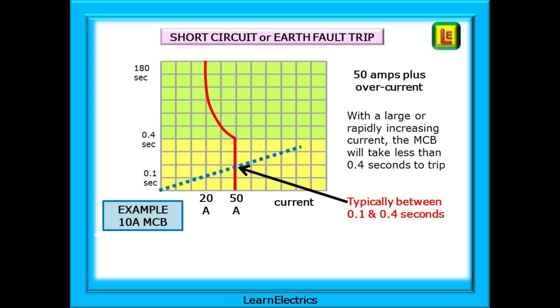But what happens with a short circuit or earth fault trip? Using the same 10 amp breaker we see that we have a rapid rise in current through the device. With hundreds of amps of fault current we very quickly exceed the 50 amp limit of current for a 10 amp device. As soon as the current exceeds 50 amps the device operates and all this happens between 0.1 and 0.4 seconds from the fault appearing. An almost instant response once the knee is reached.